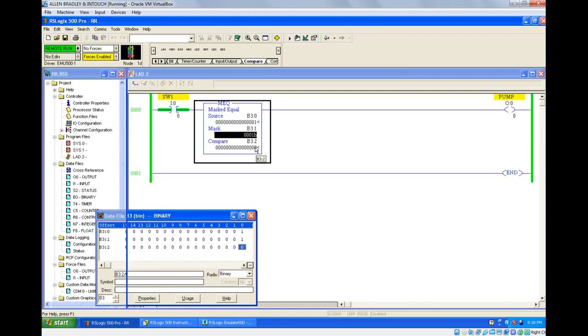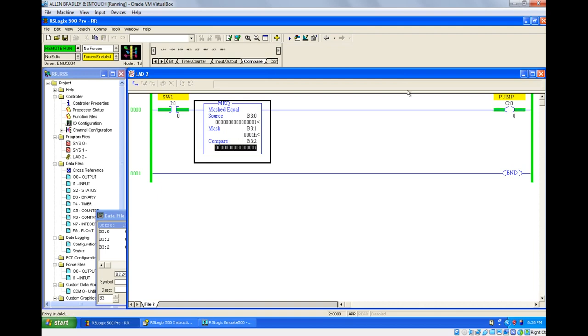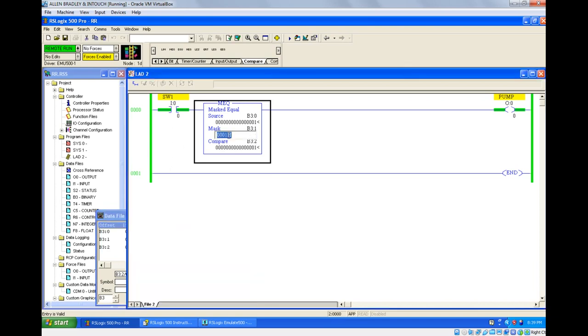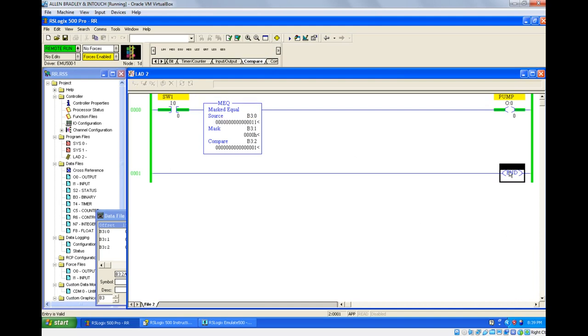Now I am changing the compare value to 1 again — now the pump is on, because the mask bit is active and both bits are equal. So if you want exact comparison and exact output, you should activate your mask bit. In some cases, even though source and comparator are not equal but you still want the output to turn on, you can deactivate the mask. I am making everything 0 now — you can see that even though source and comparator data are different, the output is still on. You can use this output for some other application in that case.